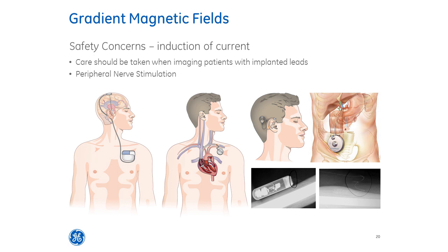Consider a stimulator implant. This is an electronic device that has leads going into an area to be stimulated and a returning lead coming back to the device, thus creating a loop. These kinds of implants were developed to deliver a very precise current, and the varying fields of the gradients could significantly alter that by inducing their own current. Therefore, the scanning of a stimulating implant is considered to be contraindicated by MR.